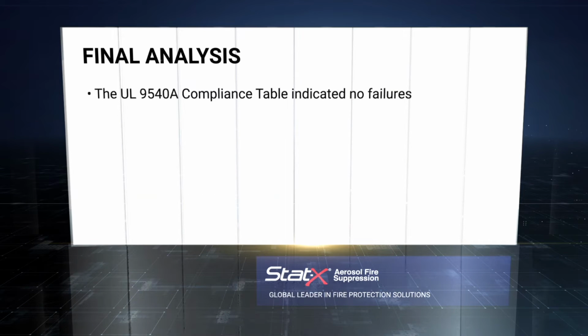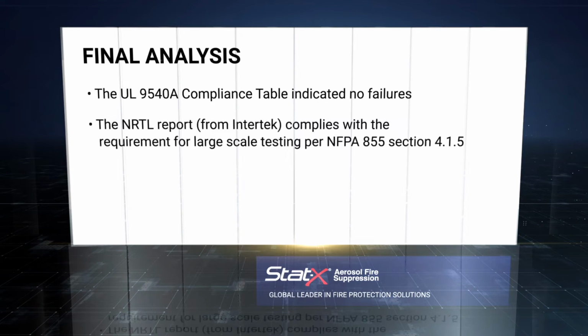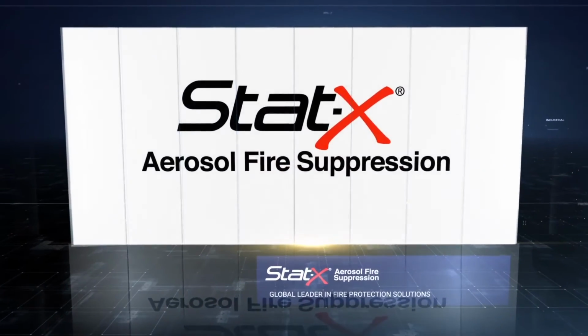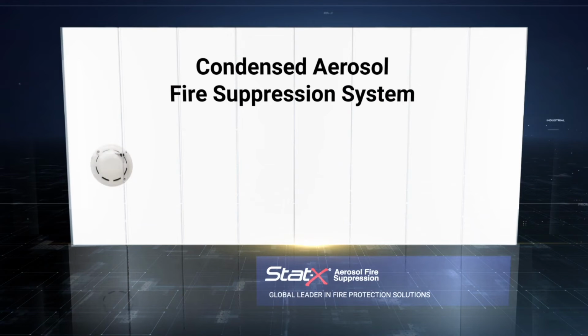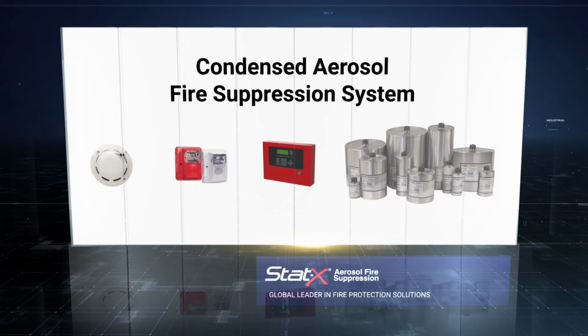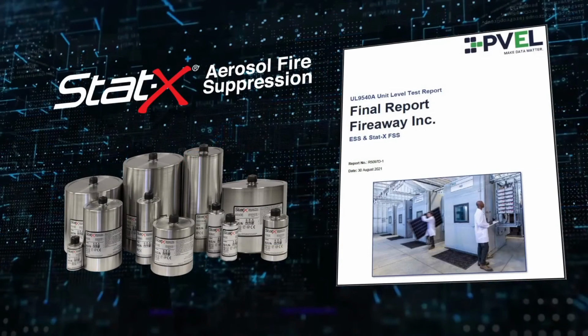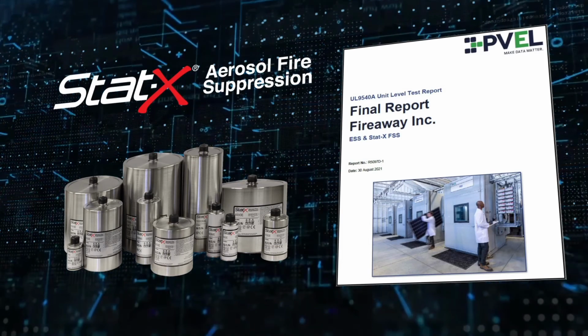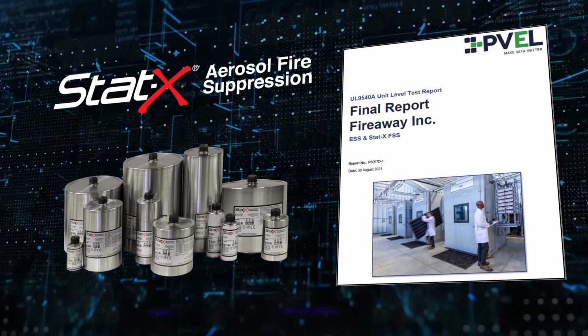The UL 9540A compliance table indicated no failures, and the NRTL report complies with the requirement for large-scale testing per NFPA 855 Section 4.1.5. These test results confirm the effectiveness of the properly designed and installed StatX condensed aerosol systems in mitigating thermal runaway propagation for ESS installations. Customers today and in the future rest easy knowing they have world-class protection for their ESS investment. For complete details of the StatX enclosure test, including criteria and the entire testing team, review the PVEL issued report.